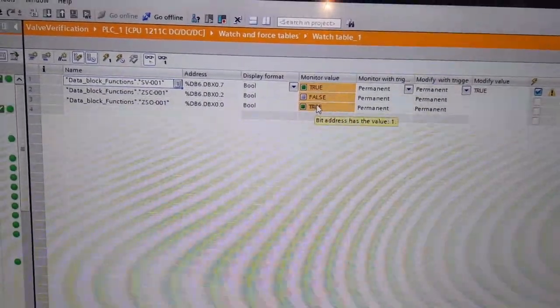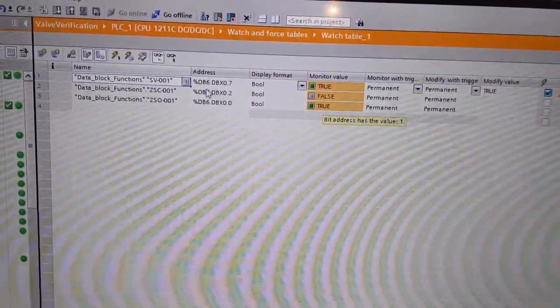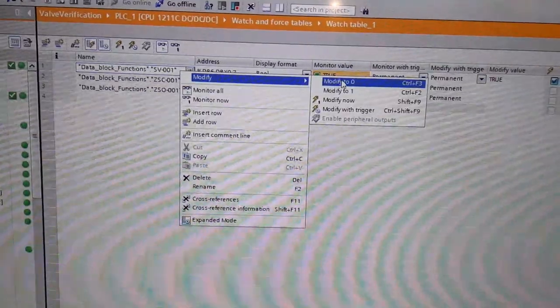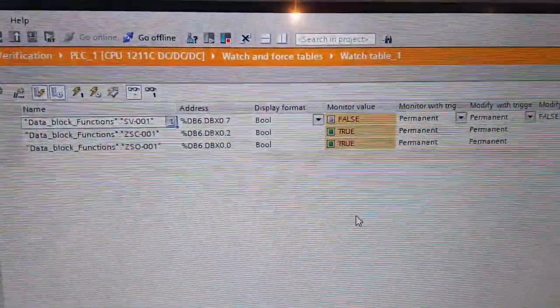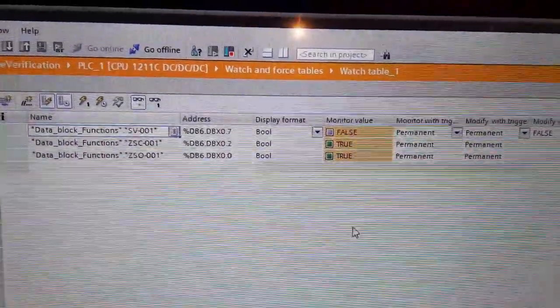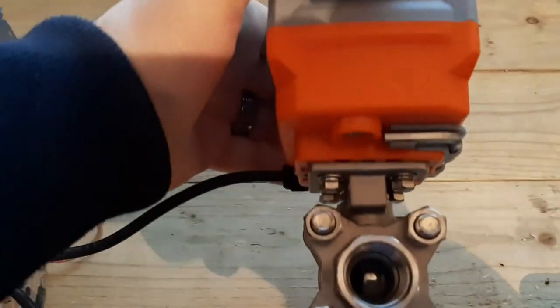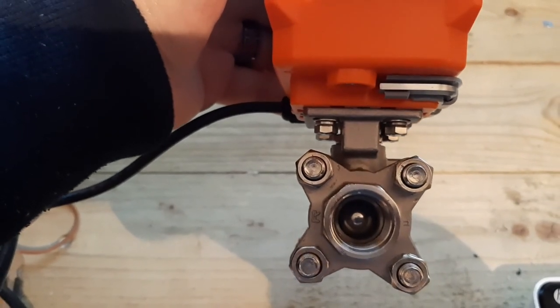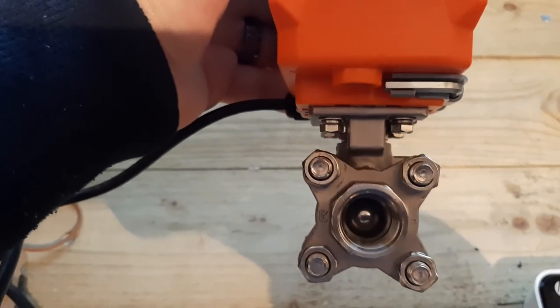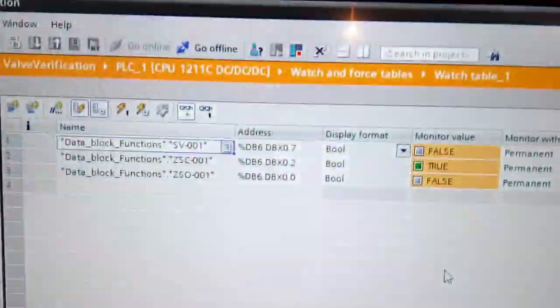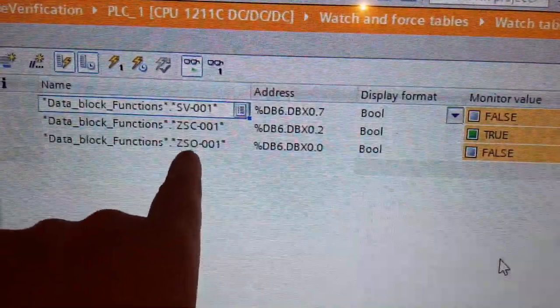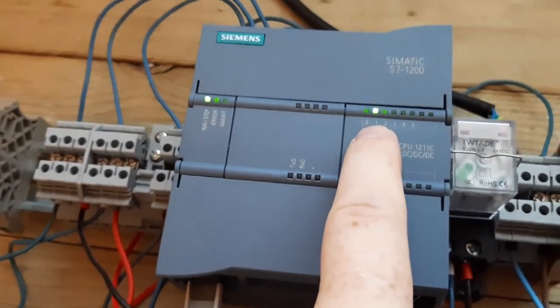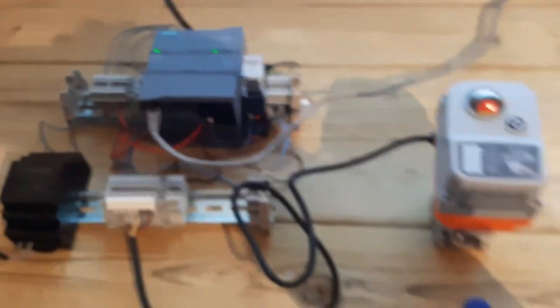You'll see there that both reed switches are true at the moment to show that it's in its intermediate state. Here we can see the valve is almost fully closed. There we go, it's fully red there giving the indication. The ZSC is true here and you can also see that the input that represents the ZSC is also true there.